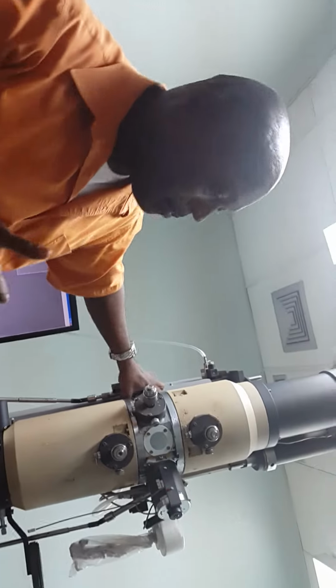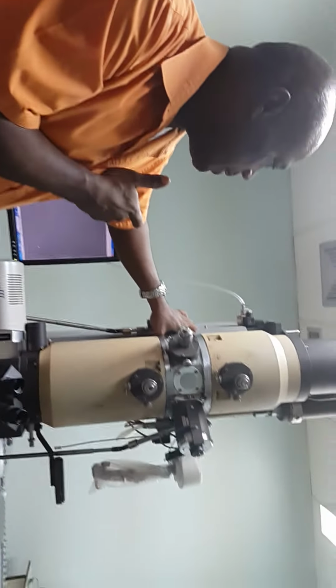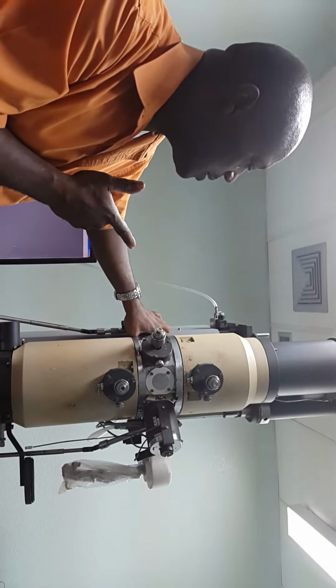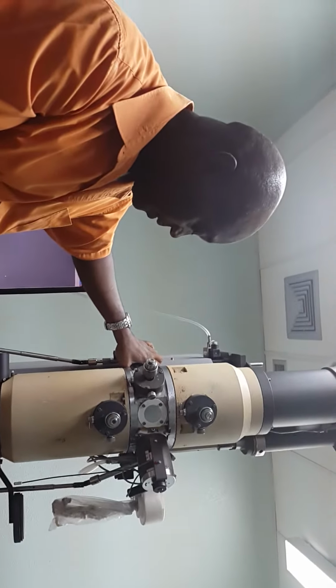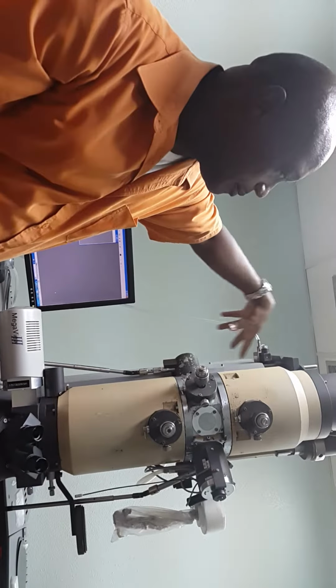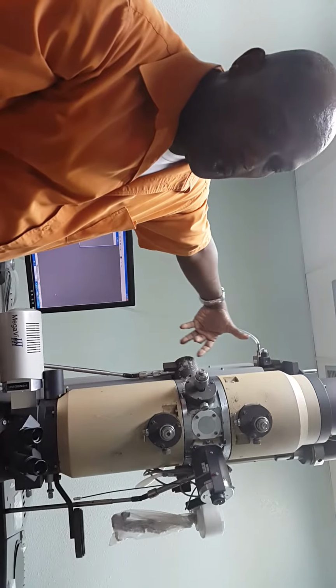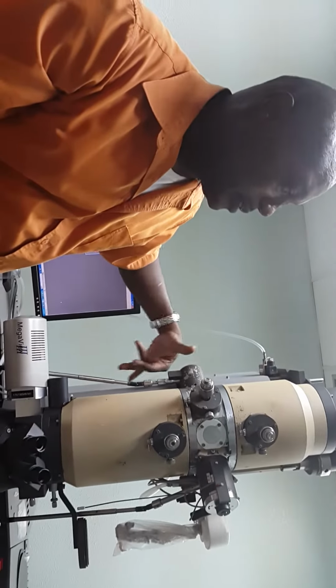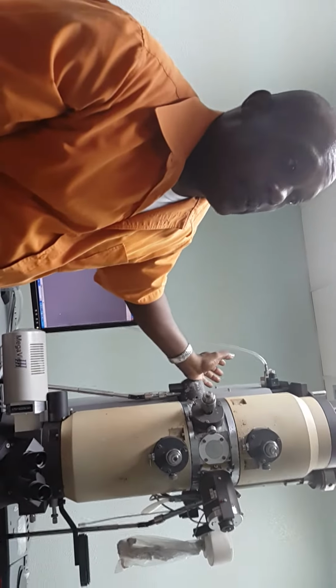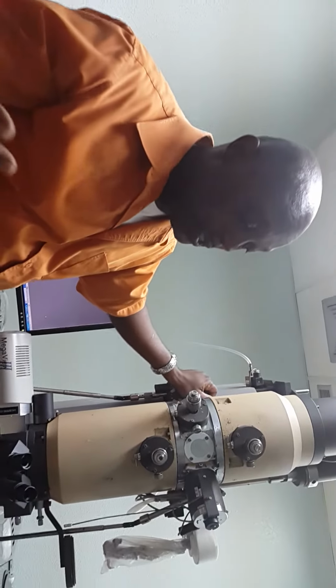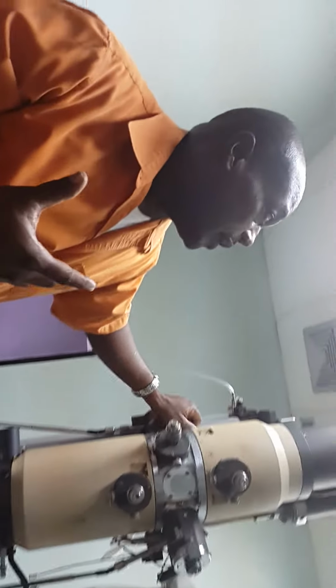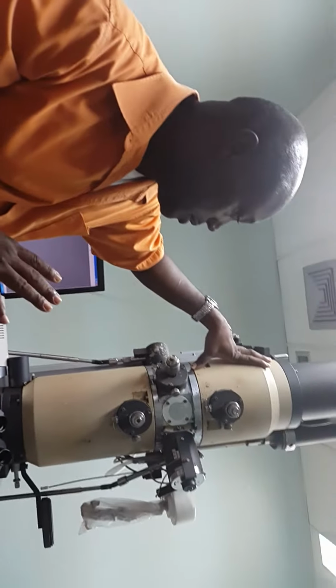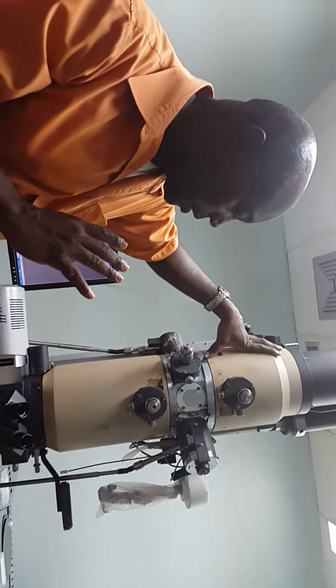There are 3 stages of pumping on this. There's a leak in the vacuum, so I have to fix that. Anyway, the pump you hear going on is a roughing pump, which goes from atmosphere to 10 to the minus 3 torr. Then it goes to the diffusion pump, from 10 to the minus 3 to 10 to the minus 6 torr. And then it goes to an ion pump, which goes from 10 to the minus 6 to 10 to the minus 10. You need a high vacuum to keep the column clean and keep the system in order.